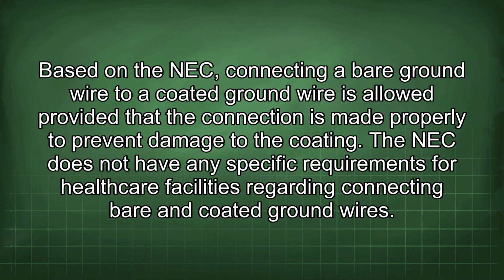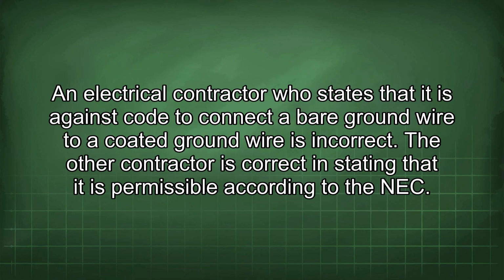Based on the NEC, connecting a bare ground wire to a coated ground wire is allowed provided that the connection is made properly to prevent damage to the coating. The NEC does not have any specific requirements for healthcare facilities regarding connecting bare and coated ground wires. An electrical contractor who states that it is against code to connect a bare ground wire to a coated ground wire is incorrect. The other contractor is correct in stating that it is permissible according to the NEC.